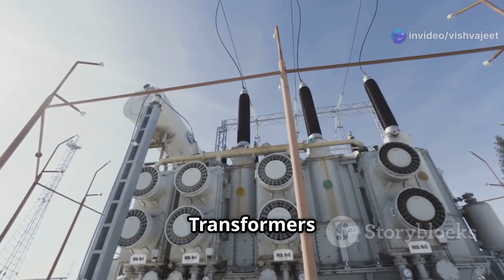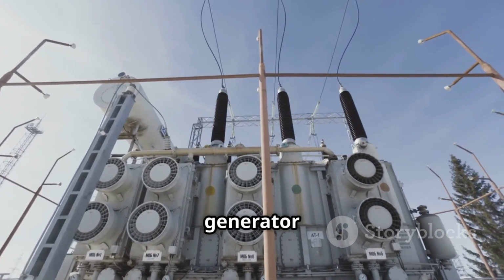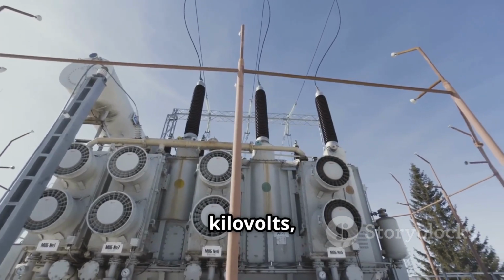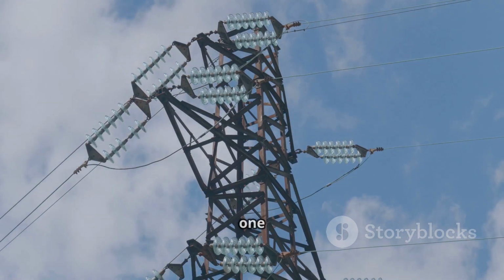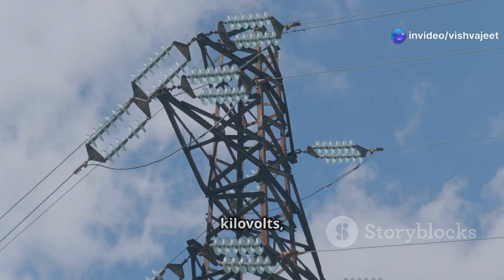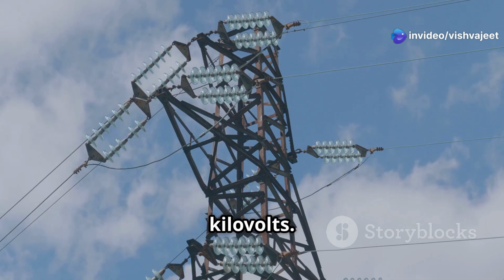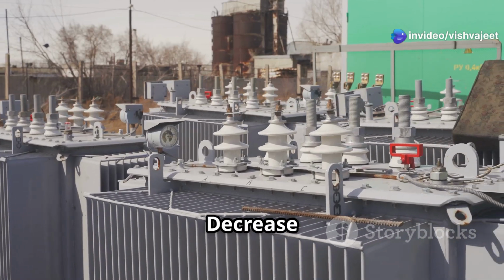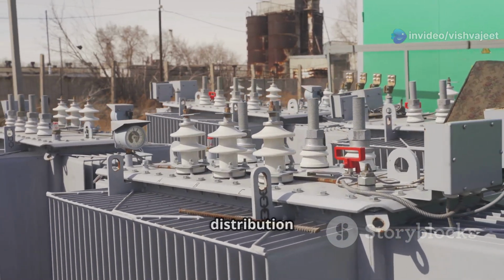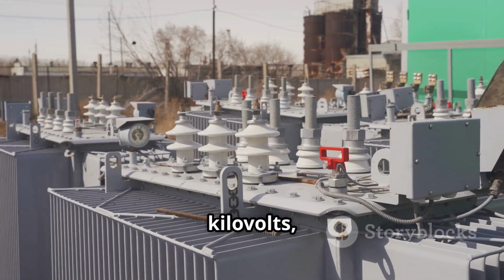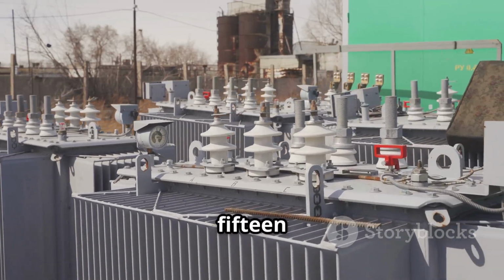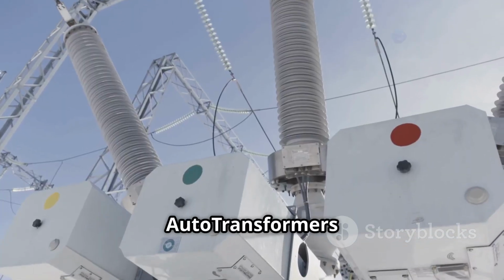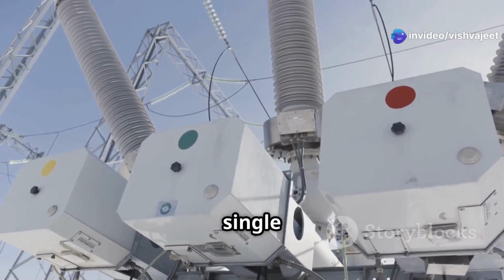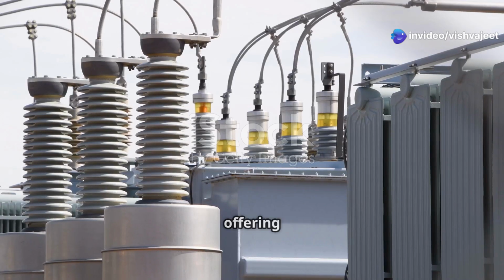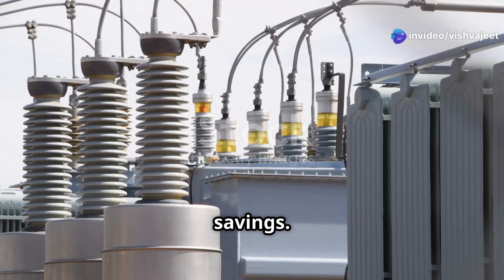Step-up transformers: increase voltage from the generator level, for example 11 kilovolts, to transmission levels like 132 kilovolts, 220 kilovolts, or even 400 kilovolts. Step-down transformers decrease voltage from transmission levels to distribution levels, such as 33 kilovolts, 11 kilovolts, or 415 volts. Auto transformers use a single winding for both primary and secondary, offering cost and space savings.